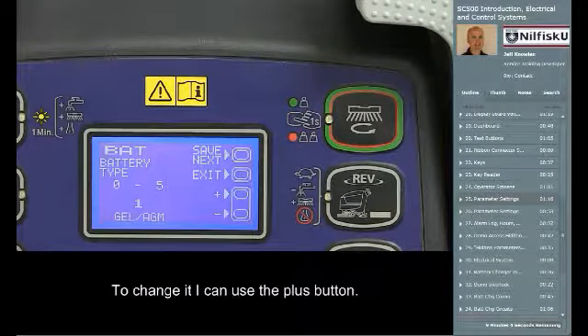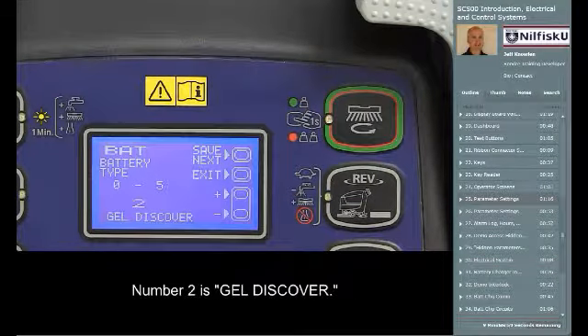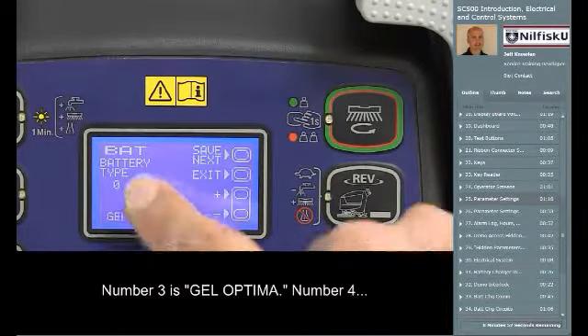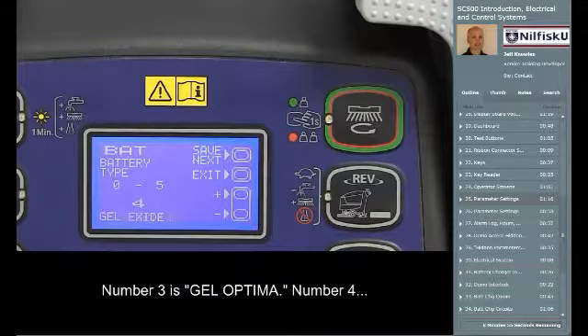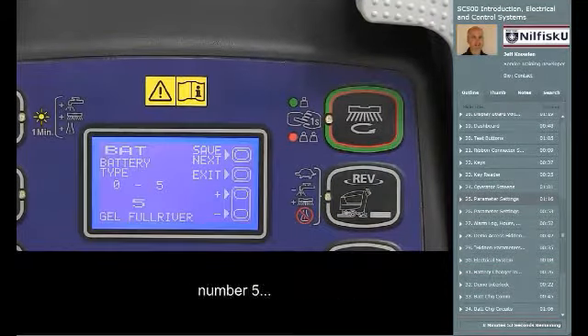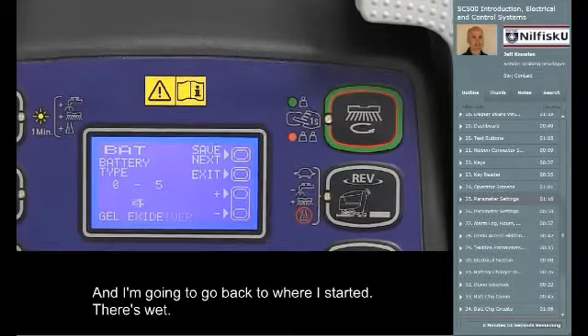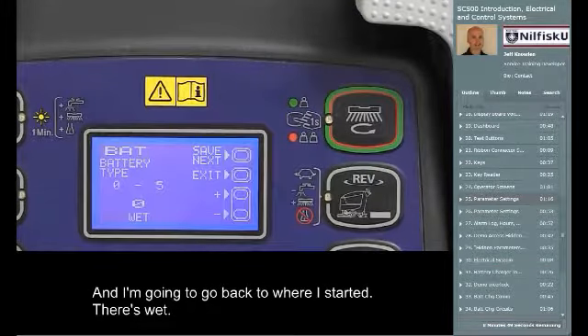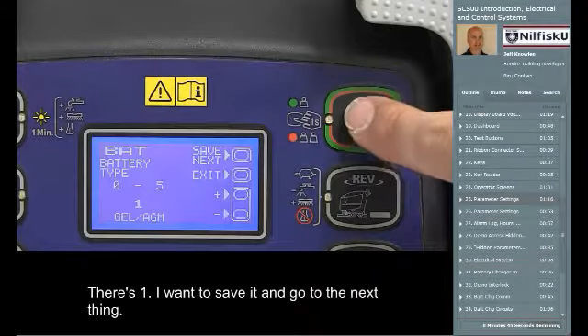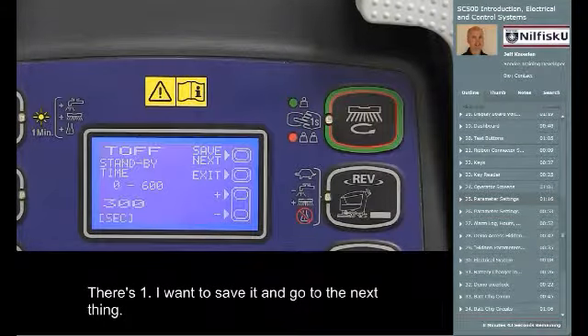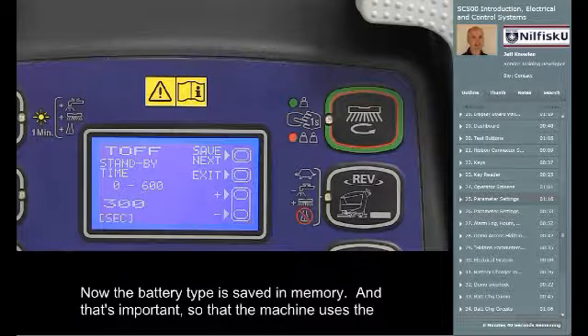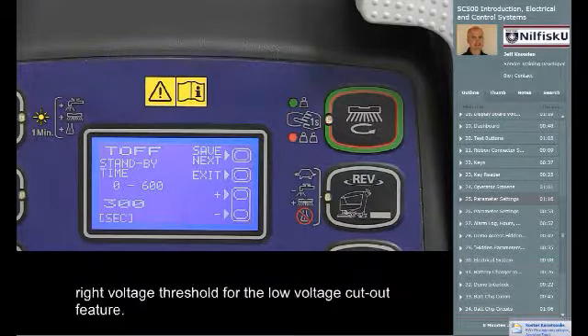But to change it, I can use the plus button. Number 2 is gel discover. Number 3 is gel optima. Number 4, number 5, and I'm going to go back to where I started. Oh, there's wet. There's 1. I want to save it and go to the next thing. Now the battery type is saved in memory. And that's important so that the machine uses the right voltage threshold for the low voltage cutoff feature.